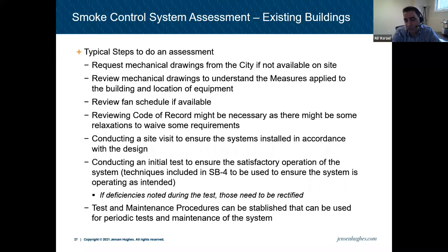And at this point, we have to do a site visit, even though we have a test result. Sometimes in 15-year-old buildings they say, oh, we have the original air balancing result. That doesn't mean anything. That system was not being maintained for 15 years. So if they tested 15 years ago and it worked, it doesn't mean that if we do the test today, it's going to pass, right? The system wasn't being maintained properly, right? So basically, we have to do that test. We call it the initial test.